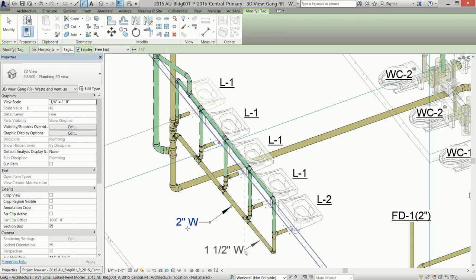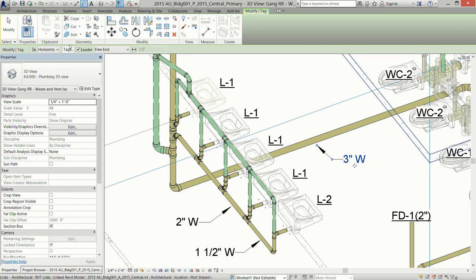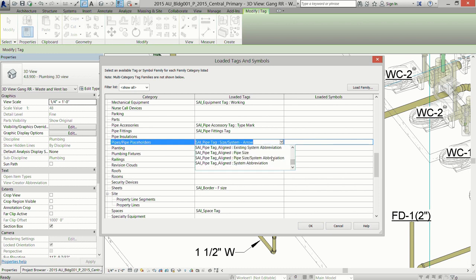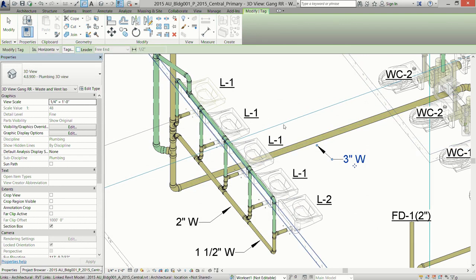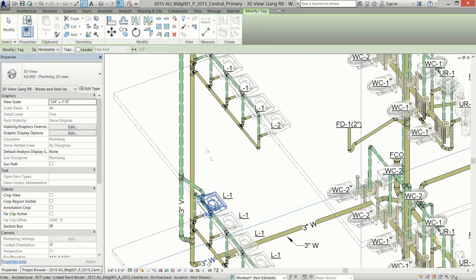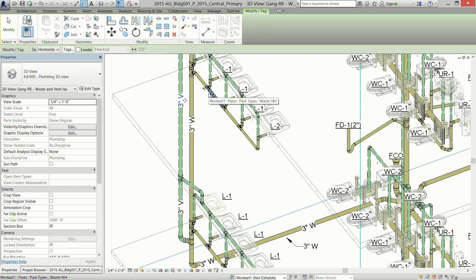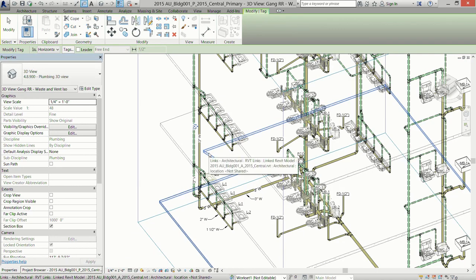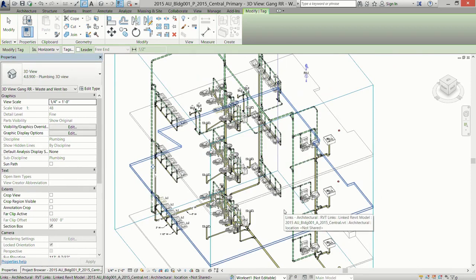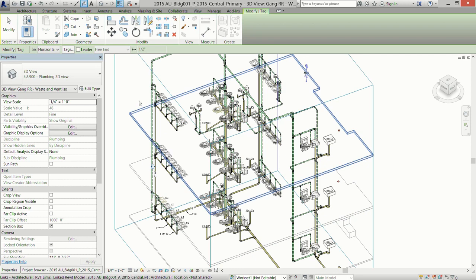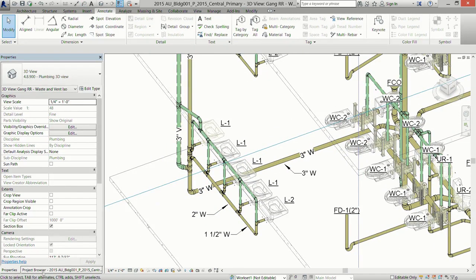So you're back to using the standard tag approach and going in tagging as you normally would on a plan. Another option we use in our office is a tag that will align with the system. You can't use it with a leader, but it's quick and fast. I normally use it on the stacks and long runs where I've got open pipe. I can get an ISO like this tagged in all the open areas in about 30 seconds. If you don't have an align tag, I would highly recommend finding or making one — it's really easy and not that difficult.